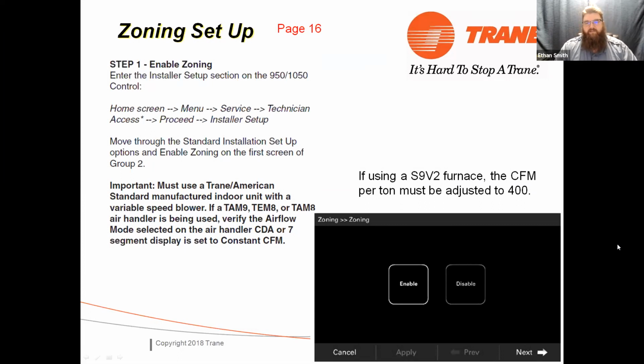Okay. So as part of the installer setup, if you've wired your zone panel up properly and it's talking to your 1050, the last option in that equipment setup screen is going to be whether you want to enable or disable zoning. You can hit enable. Couple things to be aware of. If you're using a variable speed blower that's not a communicating system, or even if it is, you must adjust your CFM per ton cooling or heat pump to 400 CFM per ton. Factory is 350. So please make sure that you are doing that. Make sure you're getting your CFM per ton in both AC and heat pump modes set to 400. That is very important.